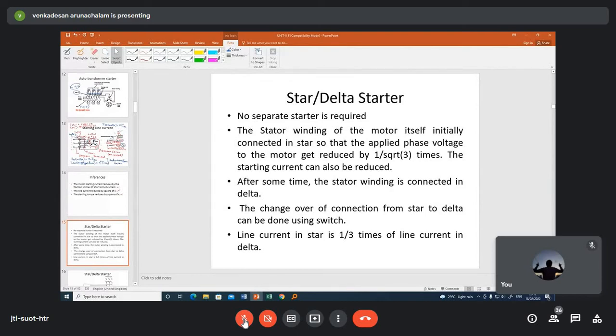So when you do this, what is happening to the motor? When you have star connection, what is the advantage? The voltage is getting reduced by √3 times. So only the reduced voltage is applied to each motor winding, because V by √3 only is applied. That is the phase voltage; the line voltage is V. And what is the voltage applied to each phase of the winding when you have star connection? V by √3. So when the stator winding is in the form of star, the voltage is reduced by √3 times. The reduced voltage is applied to the machine during starting time. Because of that, the starting current is getting reduced.